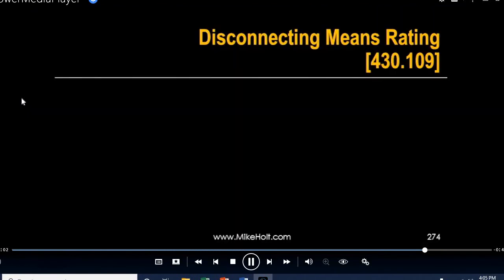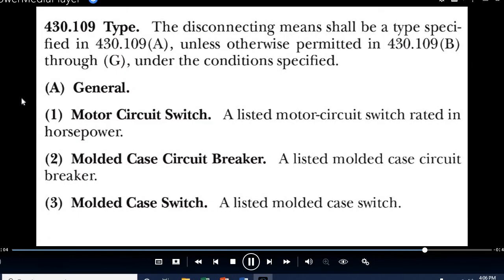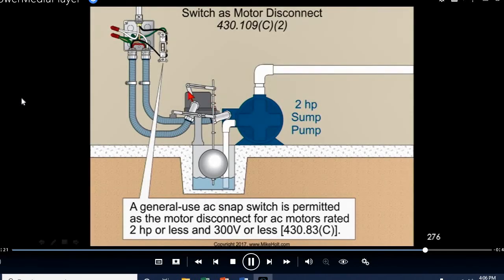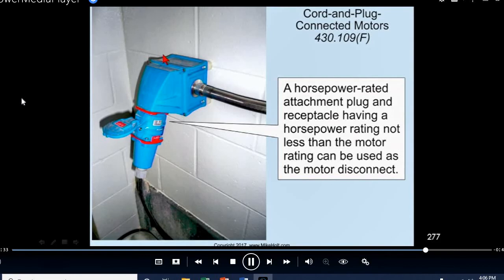430.109. Disconnecting means ratings. The disconnecting means itself has to be rated. Motor circuit switch, a listed motor circuit switch, a circuit breaker, or a molded case switch. Because why? They're automatically listed for locked rotor. They're automatically tested to the standard for that. Then we also had the condition of the switch could be used as a controller. Well, that toggle switch could also be used up to 2 horsepower as the motor disconnect. You can use a horsepower rated attachment plug and receptacle having a horsepower rating not less than the motor rating, and can be used as the motor disconnect.